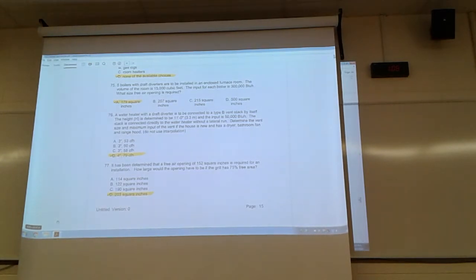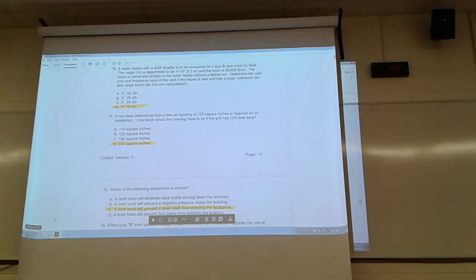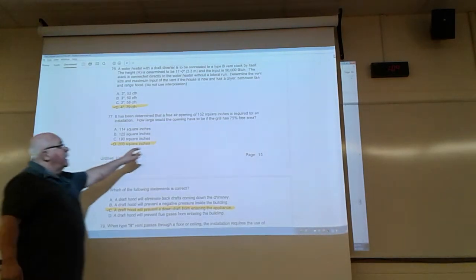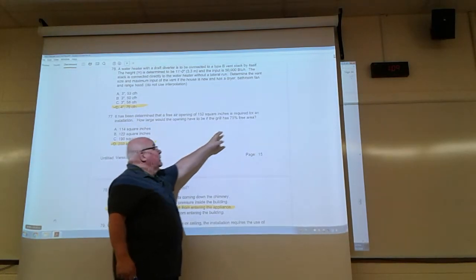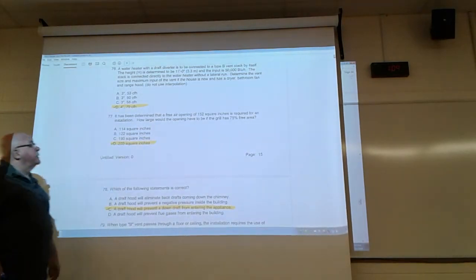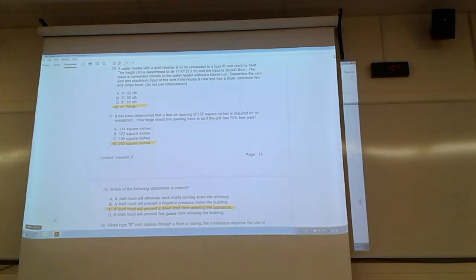Okay, everybody good? All the moaning and groaning over for 76. 77, it has been determined that a free air opening of 152 square inches is required. You have it grilled. So you take 152 square inches and divide it by 0.75, and you'll get 203 square inches. I did the calculation, I didn't trust it.